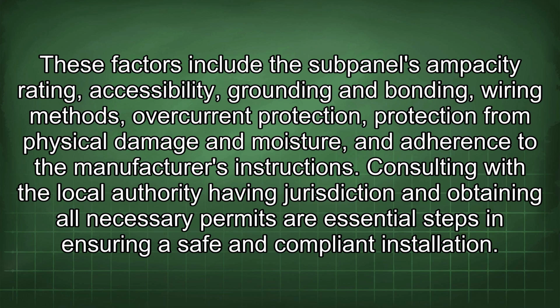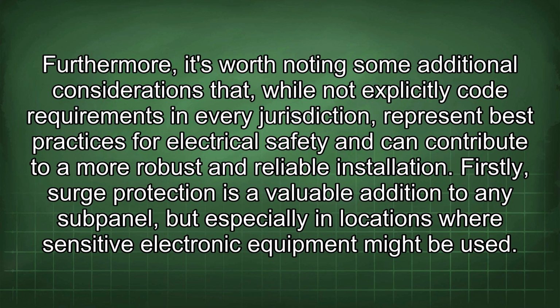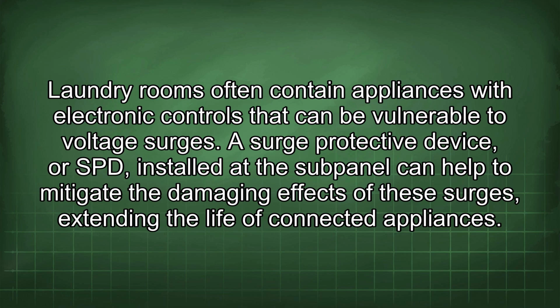compliant installation. Furthermore, it's worth noting some additional considerations that, while not explicitly code requirements in every jurisdiction, represent best practices for electrical safety and can contribute to a more robust and reliable installation. Firstly, surge protection is a valuable addition to any subpanel, but especially in locations where sensitive electronic equipment might be used. Laundry rooms often contain appliances with electronic controls that can be vulnerable to voltage surges. A surge protective device, or SPD, installed at the subpanel can help to mitigate the damaging effects of these surges, extending the life of connected appliances.